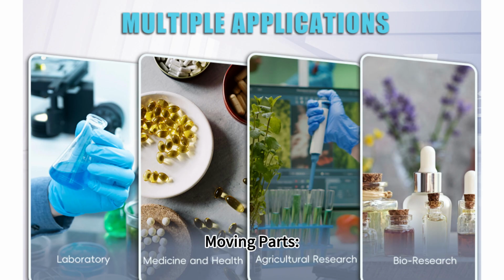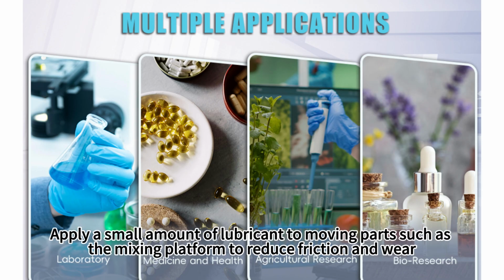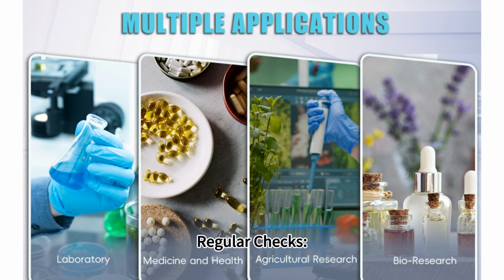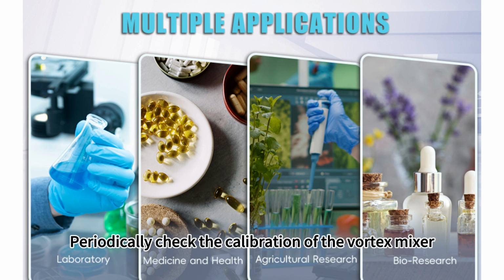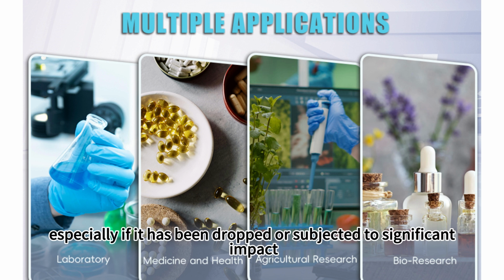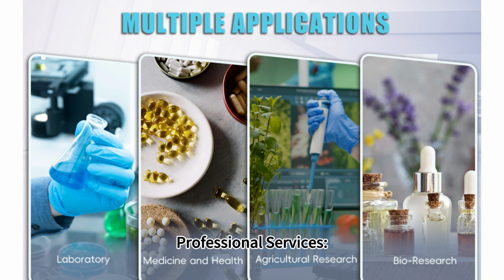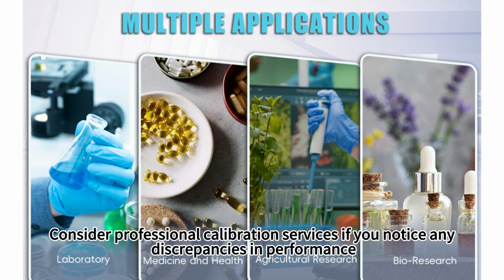Lubrication. Moving parts. Apply a small amount of lubricant to moving parts such as the mixing platform to reduce friction and wear. Calibration. Regular checks. Periodically check the calibration of the vortex mixer, especially if it has been dropped or subjected to significant impact. Professional services. Consider professional calibration services if you notice any discrepancies in performance.